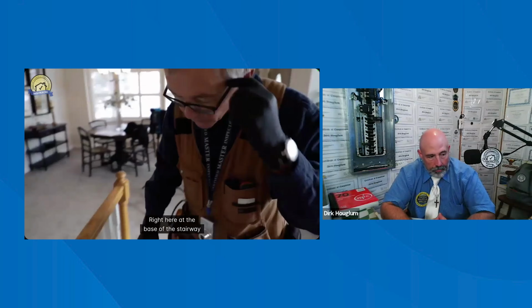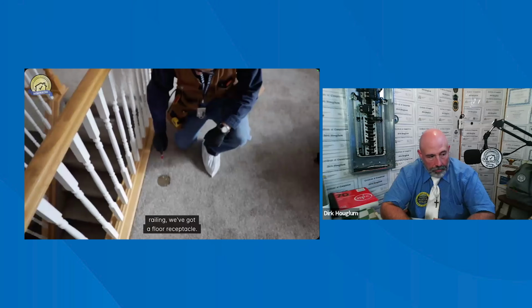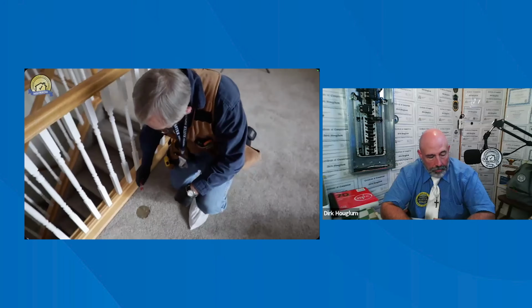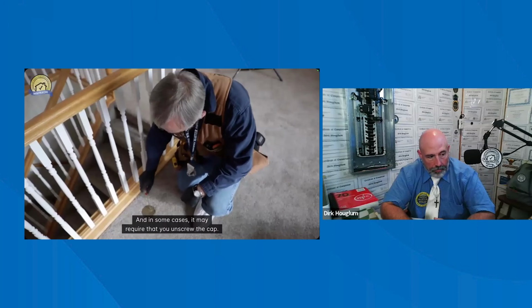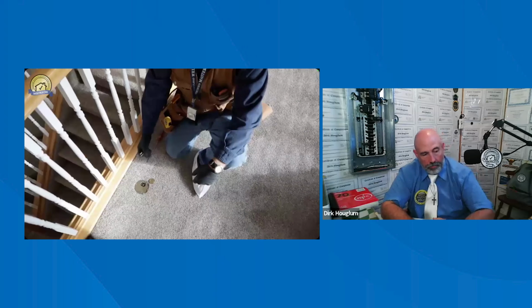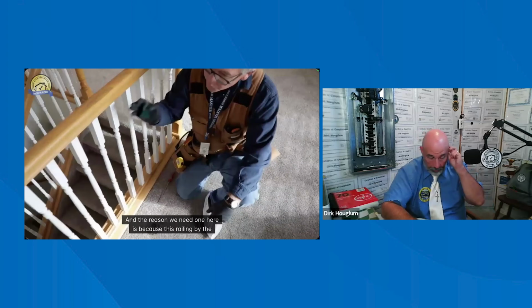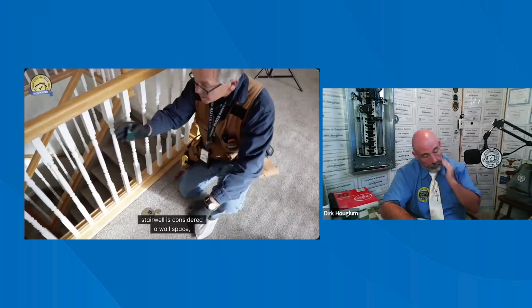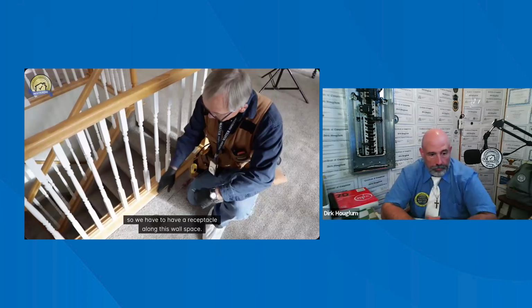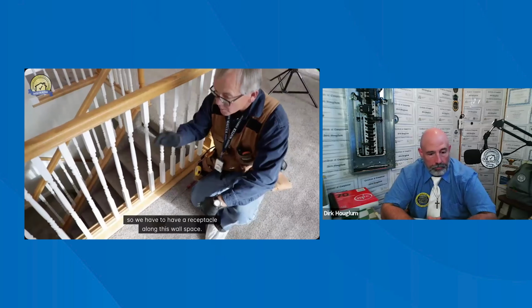Now we're going to come out here to the living room area and test a few out here as well. Right here at the base of the stairway railing, we've got a floor receptacle. In some cases it may require that you unscrew the cap. The reason we need one here is because this railing by the stairwell is considered a wall space, so we have to have a receptacle along this wall space.